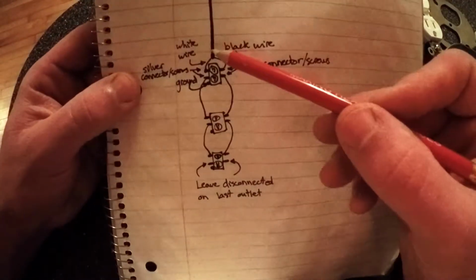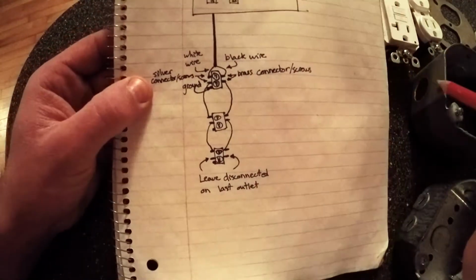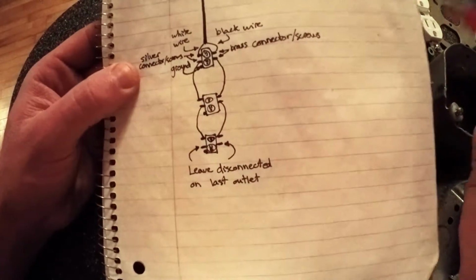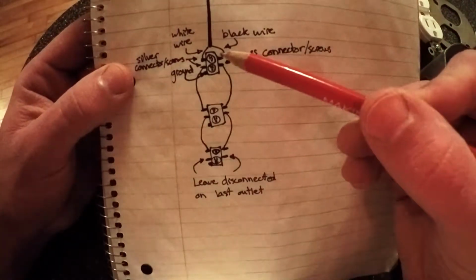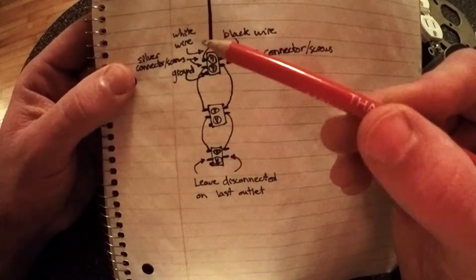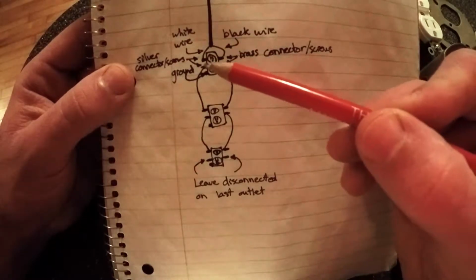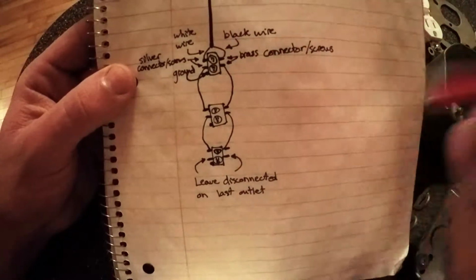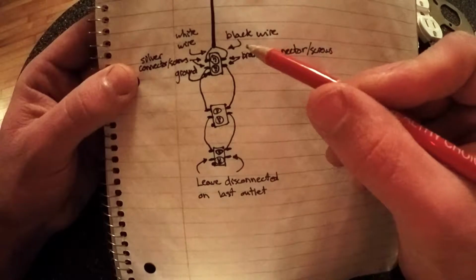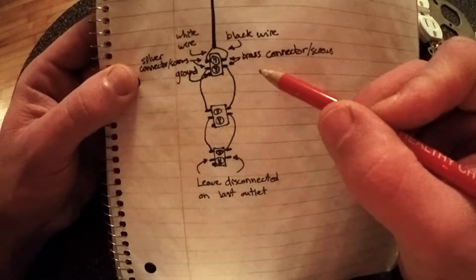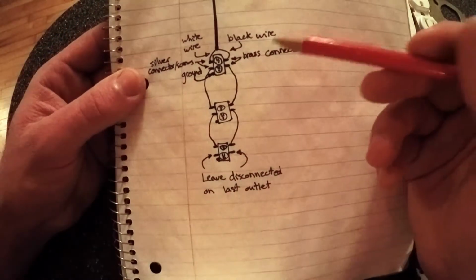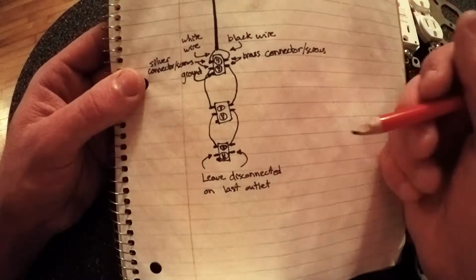Once that sheathing gets into the junction box, it goes through the side hole and is clamped into place. You're going to have these two split offs: your white wire goes to the left side when the ground is facing down, and the black wire goes to the right side, which is the brass colored screws.